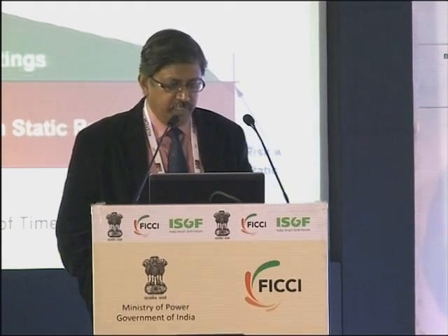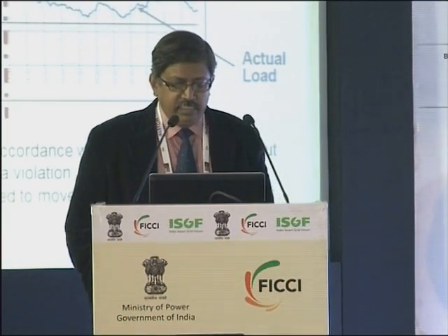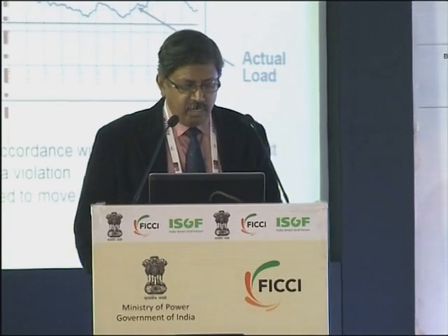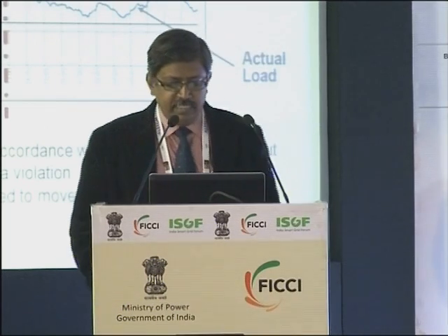You can see in the orange space, that is the static rating, as we call it. That's the normal rating of a transmission line, or I would say any distribution line as well. And the green area is the area where, by using smart grid technologies, we can extend the rating of the line for short periods of time. So here is an example where you can see the static rating, which is an orange line almost in the middle of the slide.